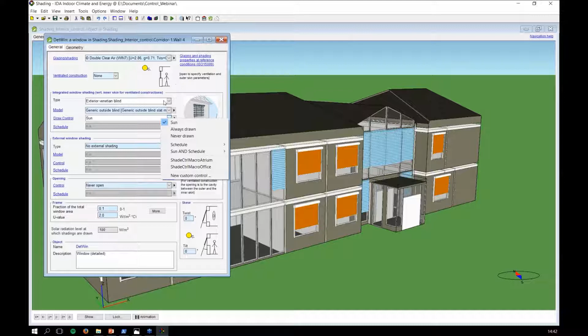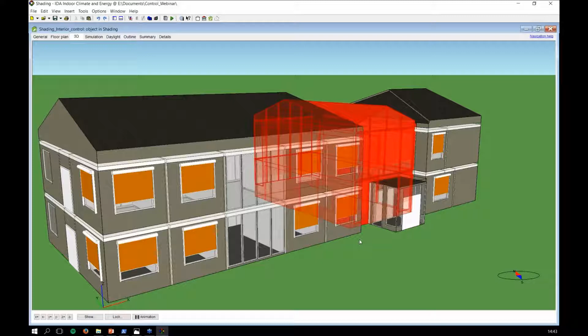Usually you would have one sensor to control, I guess it depends on the size of the building. I've seen several weather stations, but it differs a little bit. So in this case, we will show how to use one sensor to control multiple windows. I'm going to use the daylight sensor located inside this Office 7 room to control all the orange shades, while using the sensor located in the atrium zone to control the blue shades, the atrium shades.